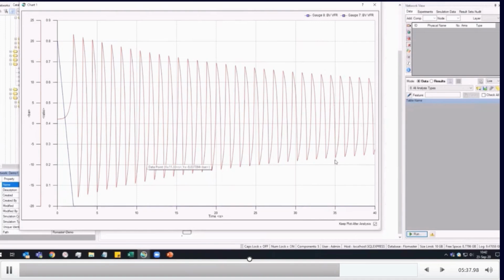This is the pressure pulse just banging up and down in this pipe. Very, very destructive. If you see, the pressure peaks at 21 bar - that's huge, that's 21 atmospheres - really, really destructive to piping network systems and something you want to avoid at all costs, okay?